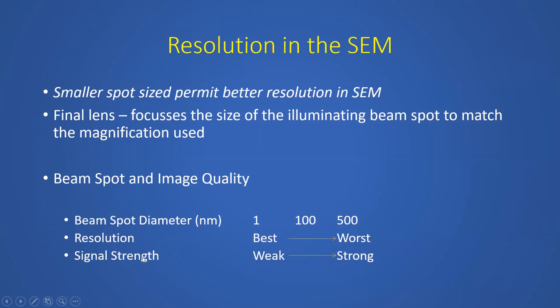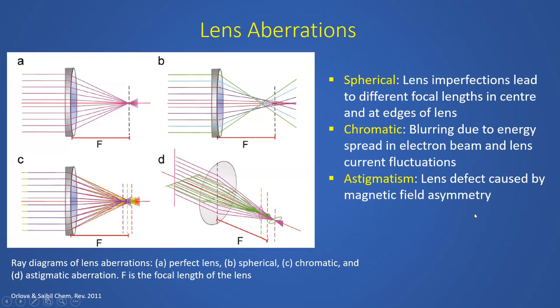Resolution in the SEM depends totally on the spot size. The smaller the spot size, the better the resolution. Typically, the final lens is used for focusing the size of the illuminating beam spot to match the magnifications that are used. That's why the final lens, condenser lens 3, is the most important lens, and it is responsible for the final spot size that you get at the specimen level. You can see here the spot diameter: 1 nanometer, 100 nanometer, 500 nanometer. As the spot size increases, the resolution decreases. This goes from best to worst, and the signal goes from weak to strong. You get a stronger signal but worse resolution, so you have to play around with the parameters to get the best results. But the important thing is that the spot size will determine the resolution of the SEM.